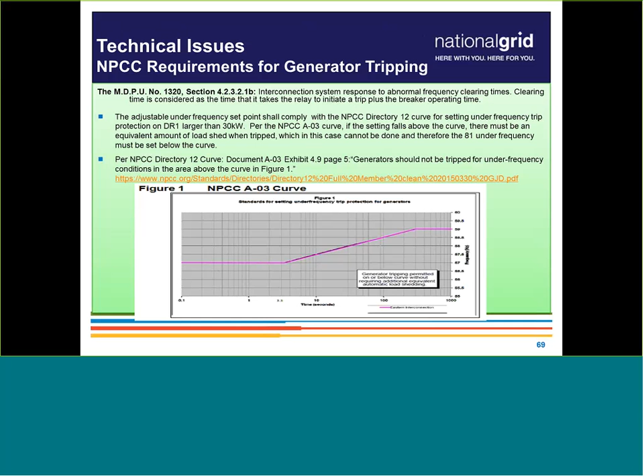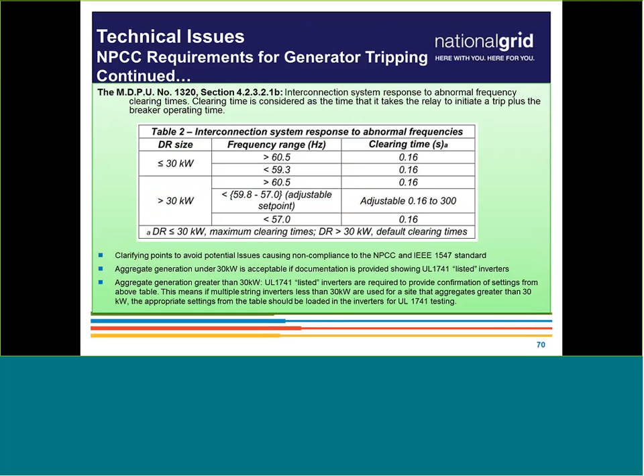User settings for complex projects greater than 30 kilowatts that we look for - we look for these on your one line. This is something unlike the overcurrent relays, which you can get right off the bat. You should never be swinging in the dark when proposing these under and over frequency settings, because this is what you've got to follow.